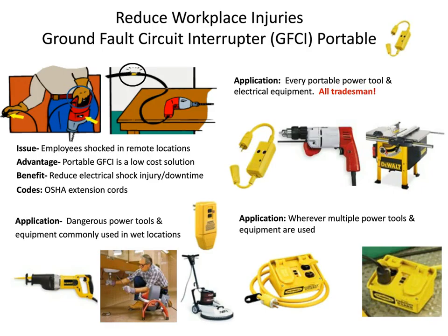So the ground fault receptacle basically is going to monitor the load, what's coming back on the neutral. If there is a leakage between 4 and 6 milliamps, the ground fault will trip and theoretically save the person. When we get into portable ground faults, there's one difference between a portable ground fault and a receptacle. In a portable ground fault, as we see here, there are several illustrations of portable ground faults here. Portable ground faults have an open neutral relay. And I'll talk about what an open neutral relay is for you in a second.